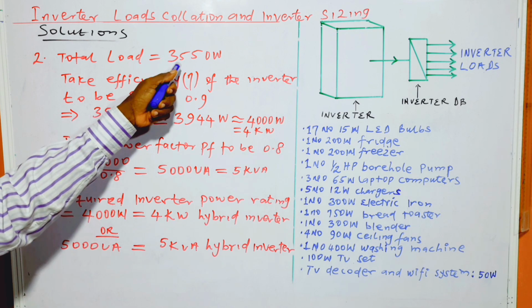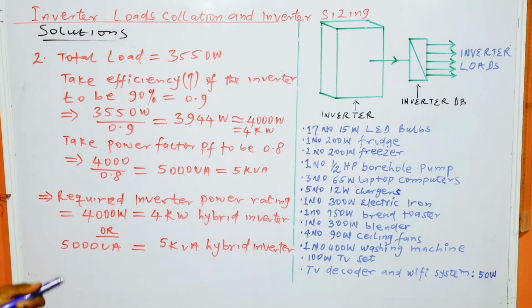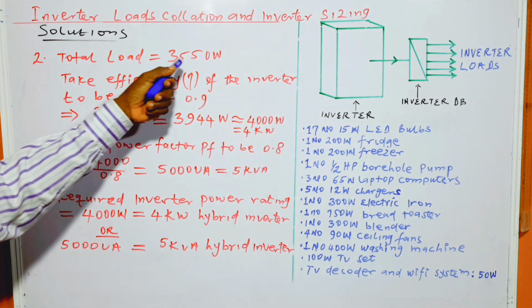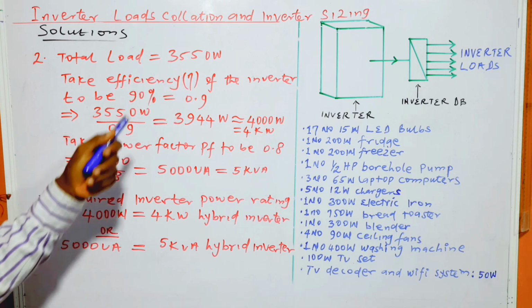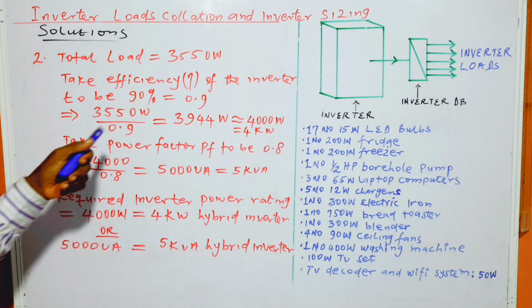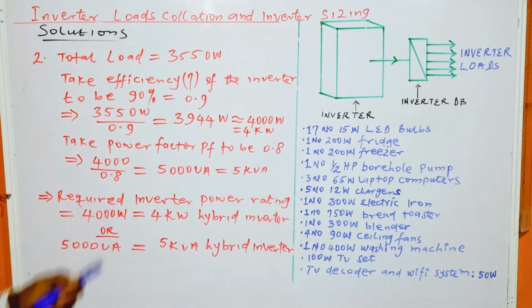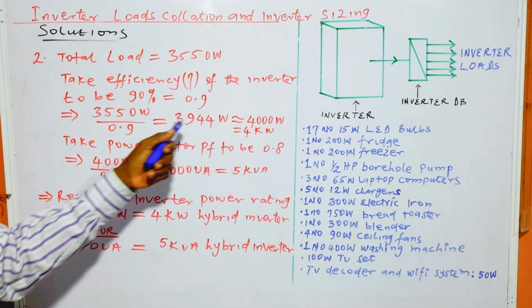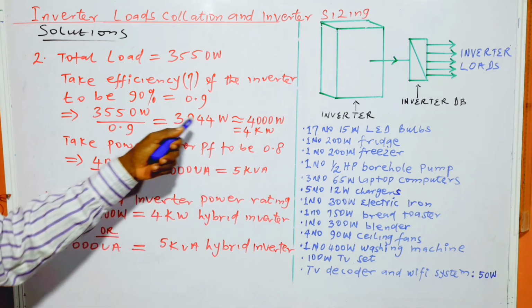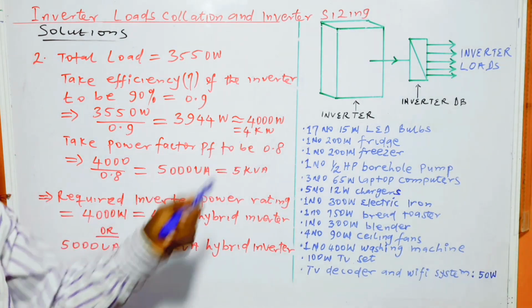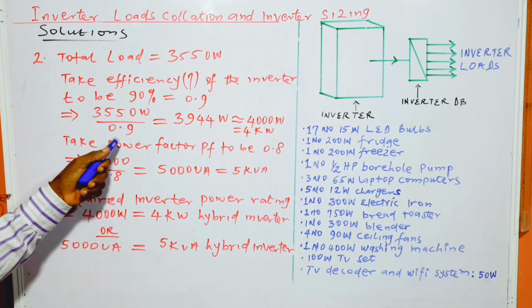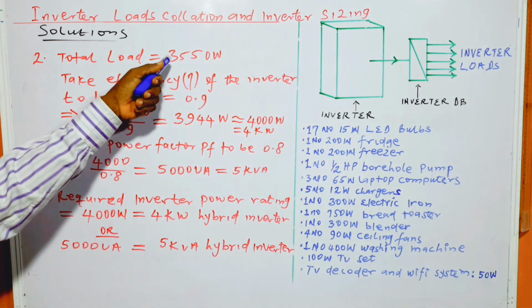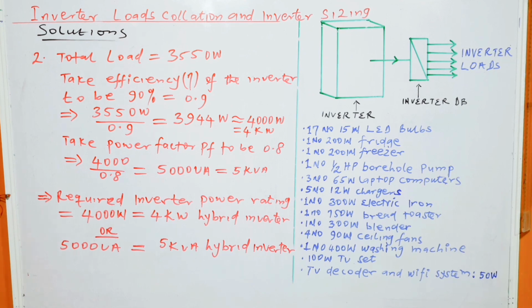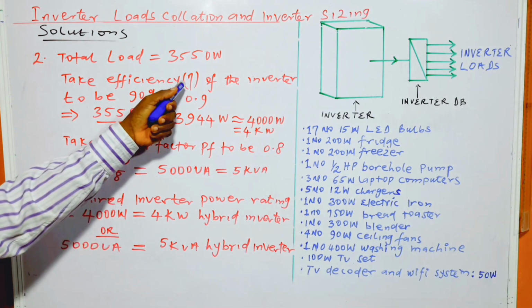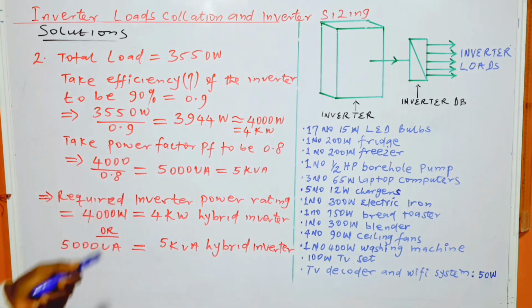Now, the second question. Total load is equal to 3,550 watts. Then we take into consideration losses in the inverter itself. If we are to get this amount of power going to the load, and the efficiency is 90%, then the input to the inverter must be approximately 4,000 watts, which is 4 kilowatts. This is how it's calculated: you divide this power by 0.9, which is the efficiency. That is the symbol for it.